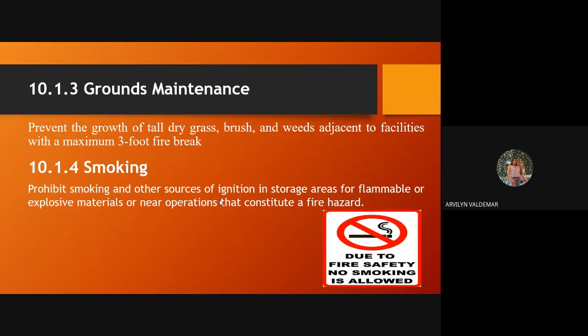Ground maintenance. Prevent the growth of tall, dry grass, brush, and weeds adjacent to facilities with a maximum 3-foot fire break. Next is smoking. Prohibit smoking and other sources of ignition in storage areas for flammable or explosive materials or near operations that constitute a fire hazard.